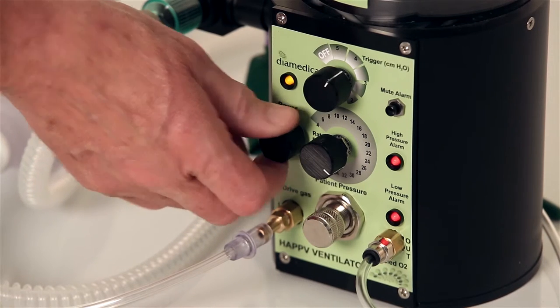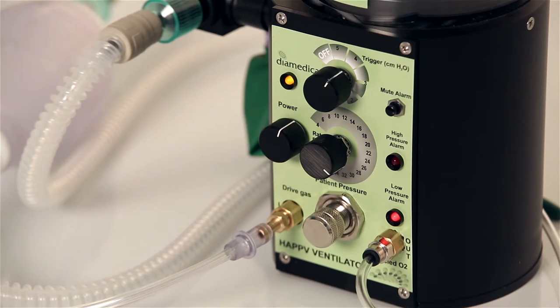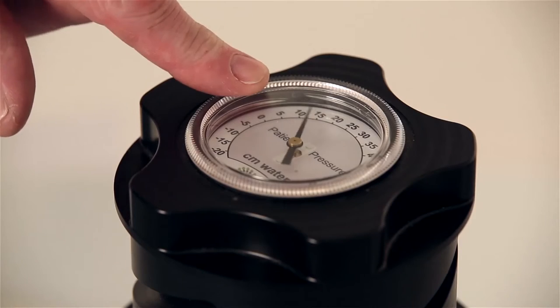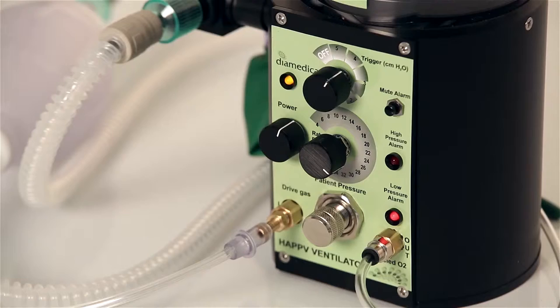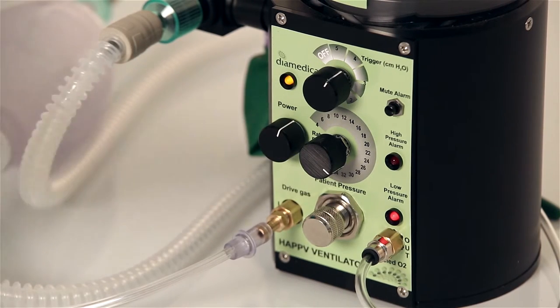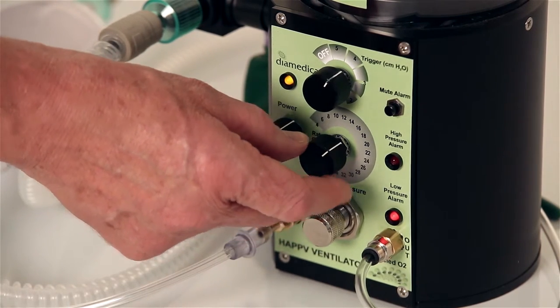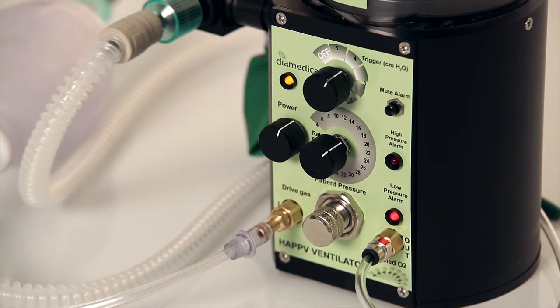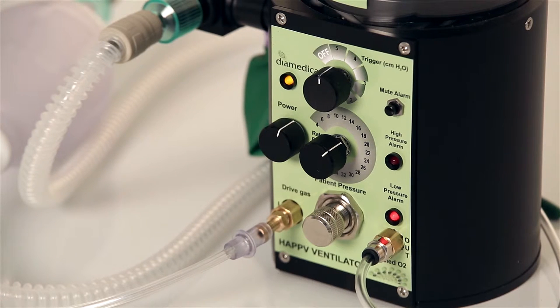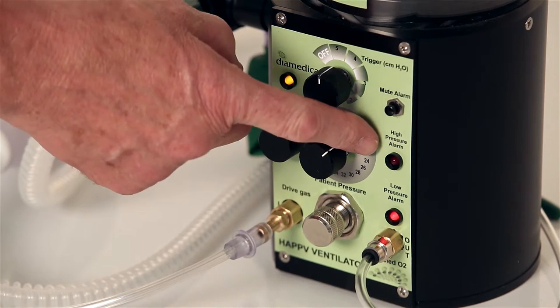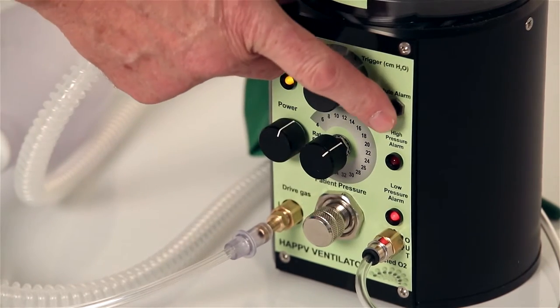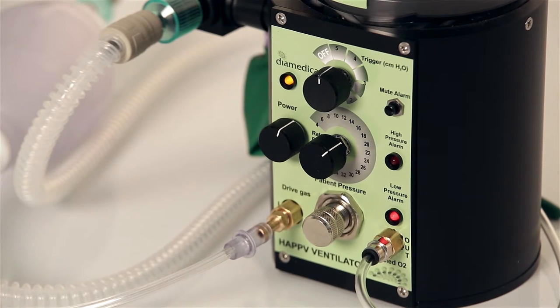There is an on-off control with a power-on light and a patient pressure control with the pressure gauge mounted in the top of the helix screw. There is a breaths per minute control that will provide a rate from 4 to 40 breaths per minute by simply turning it to the desired setting, and a triggered breathing control to assist weaning or to provide pressure support. There is an alarm for high pressure and low pressure or disconnect alarm with a mute for the audible low pressure alarm.